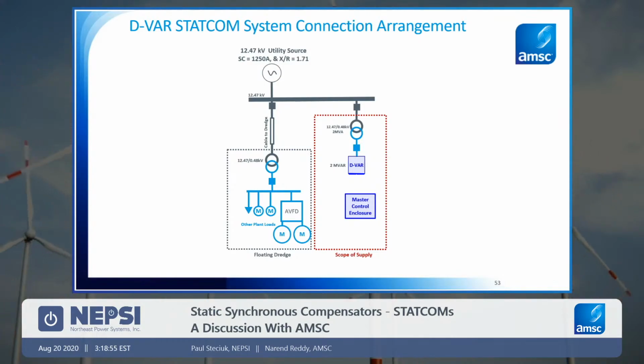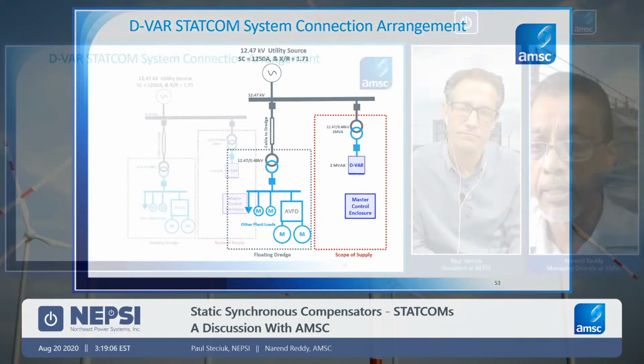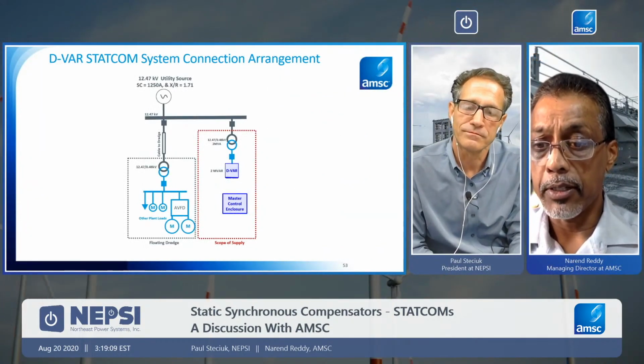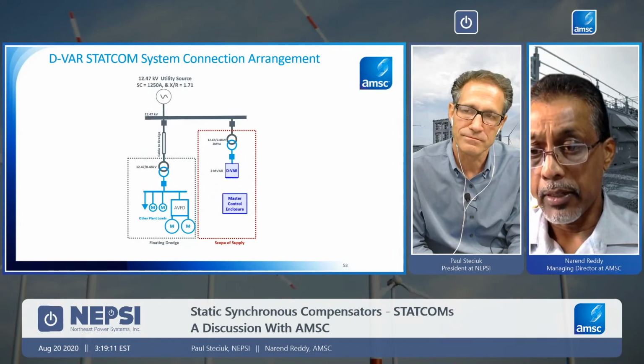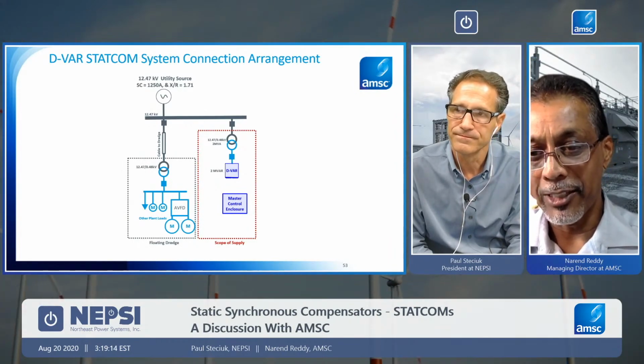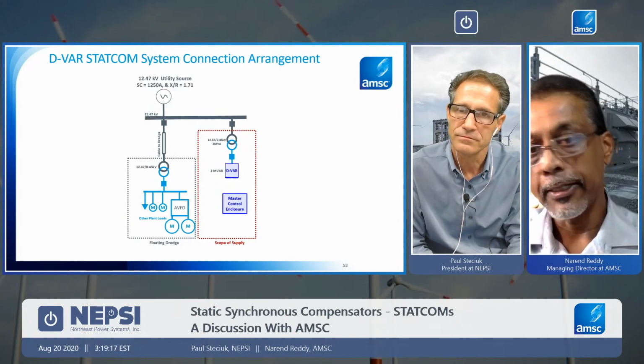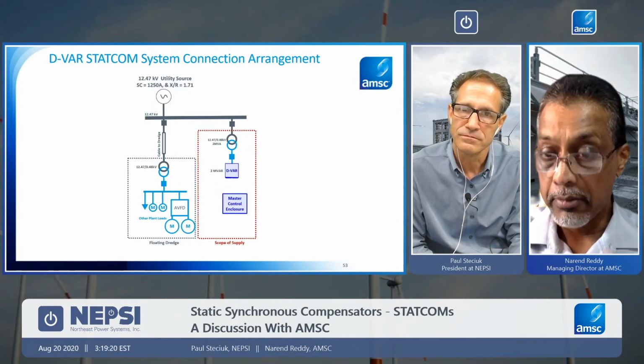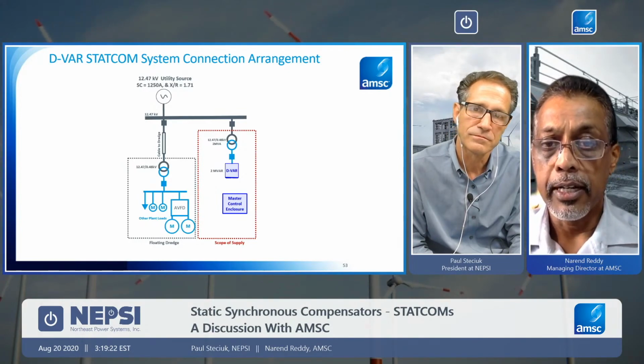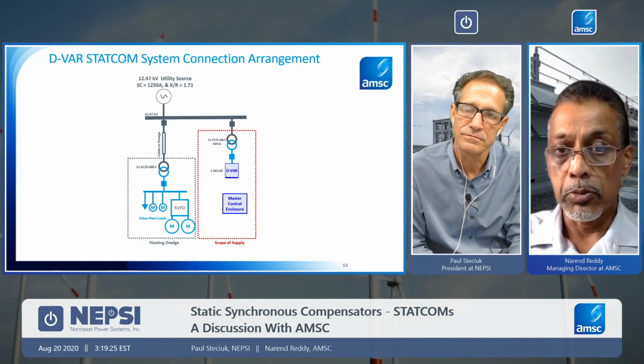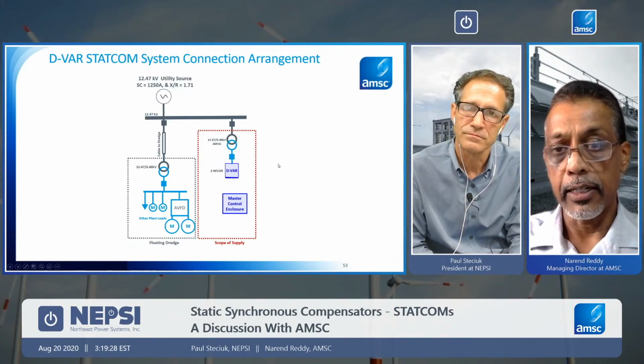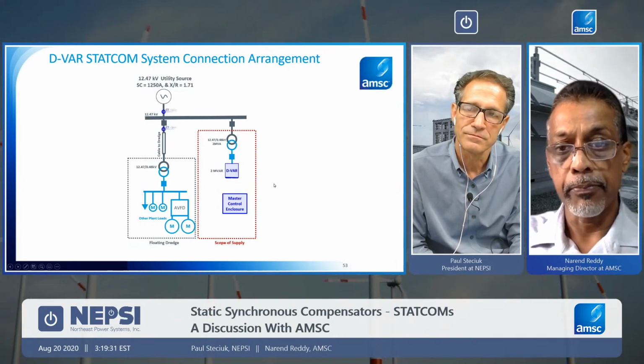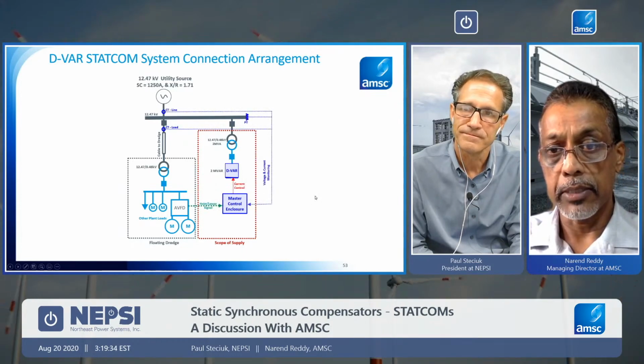Because it's a 2 MVA requirement, a 2 MVA transformer is purchased for that. The D-VAR is 2 MVA. I've shown you pictures of a 4 MVA D-VAR as a building block. We would use the same building block, same enclosure and everything, except the number of inverters inside is half, so it's half populated. Some customers choose to upgrade their system later on, and that's an option for them as well. So, a 2 MVA D-VAR connected to a 2 MVA step-up transformer, with a master control enclosure, which is installed.